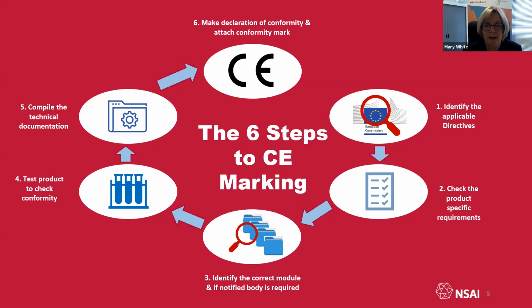Module A would normally be associated with self-certification. And then you may need to contact a notified body for third-party certification. You then have to test the product to check conformity. That could be at an INAB test lab or a UKAS test lab. And then you must compile the technical documentation. And finally, you have your declaration of conformity and you're able to attach your conformity mark.